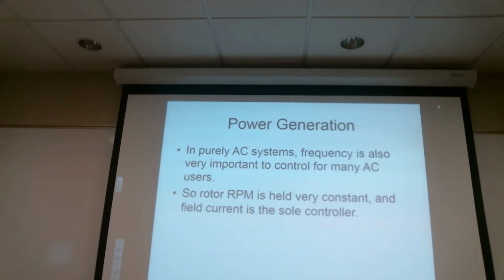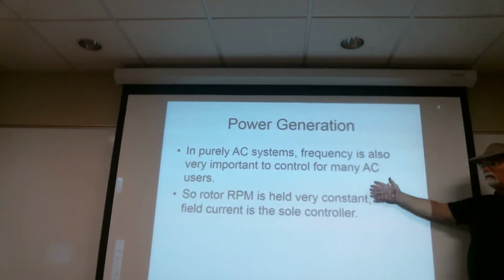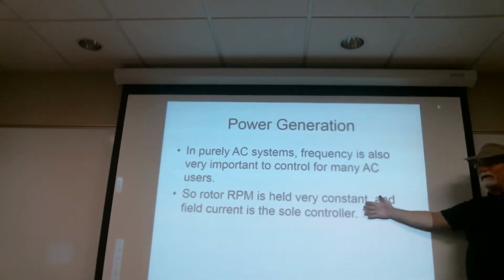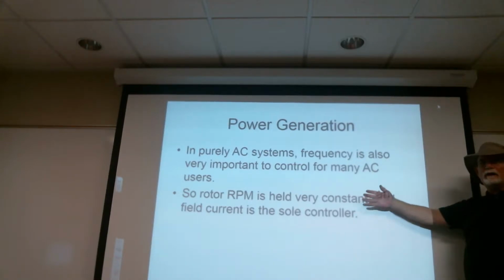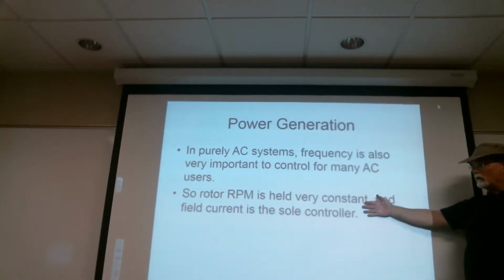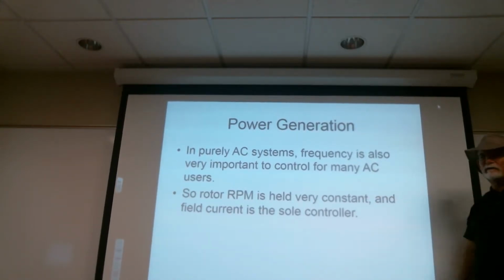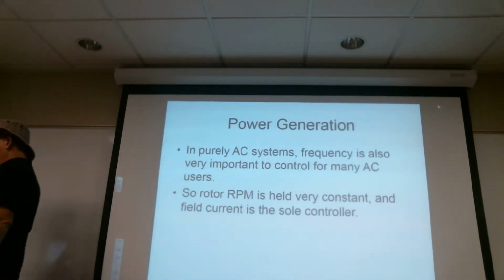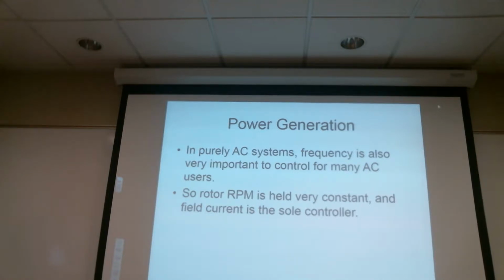Okay, so where AC matters, we have to keep rotor RPM very, very constant, whether it's a field spinning or armature spinning. If we go hit the button right there and see the actual frequency, you'll see it's 59.998 or 60.002, plus or minus 0.002.